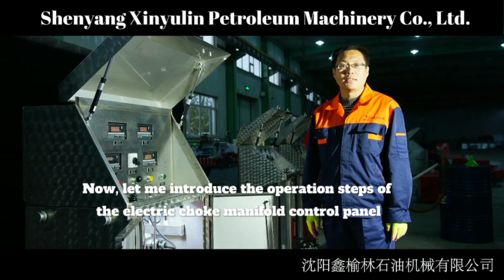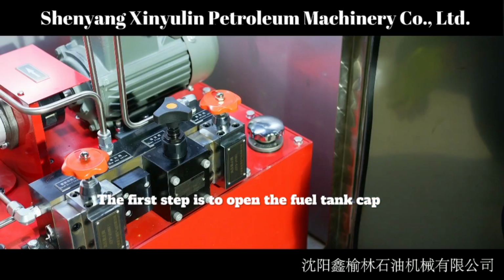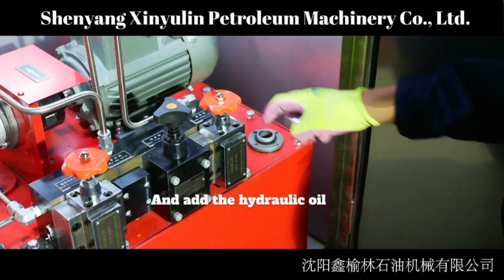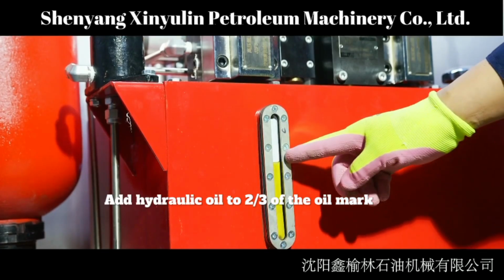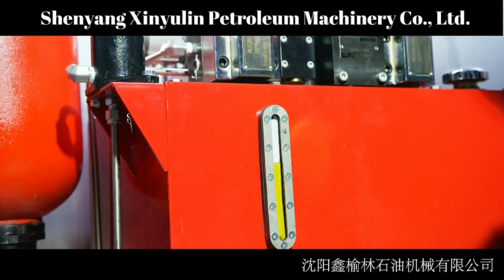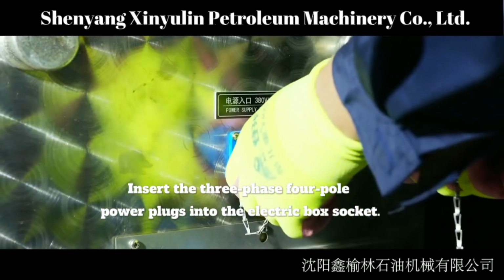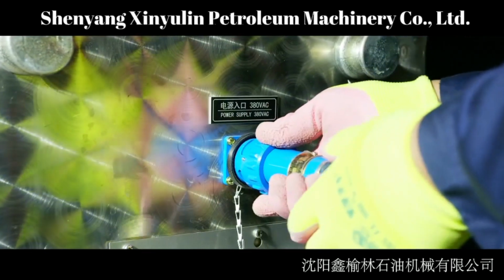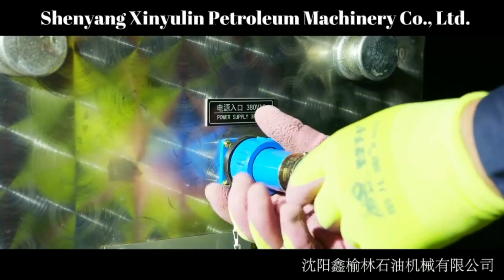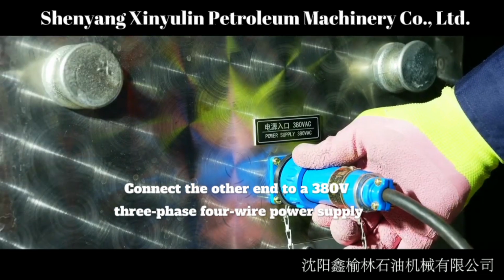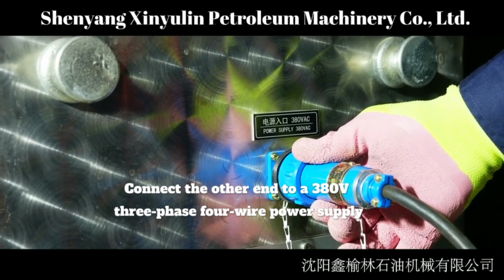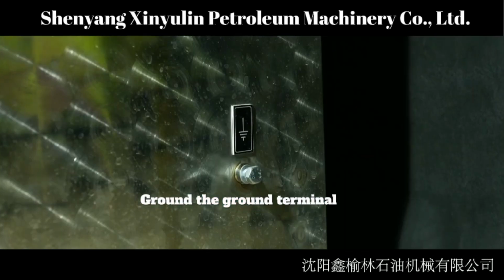Now, let me introduce the operation steps of the electric choke manifold control panel. The first step is to open the fuel tank cap and add the hydraulic oil. Add hydraulic oil to 2/3 of the oil mark. Insert the 3-phase 4-pole power plug into the electric box socket. Connect the other end to a 380V 3-phase 4-wire power supply. Ground the ground terminal.